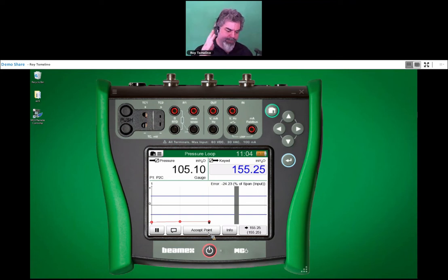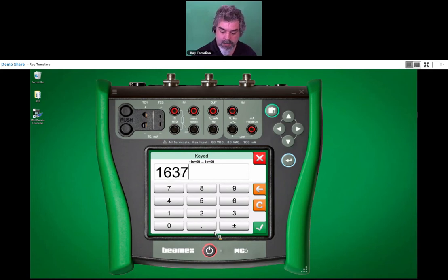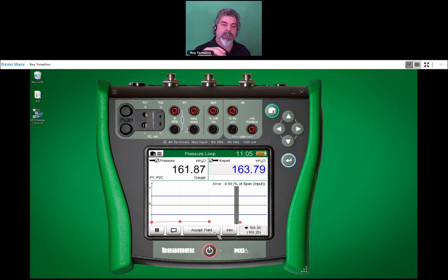So what do? As long as everything is connected correctly, I need to go to 155 now. As long as everything is connected correctly, then I just way overshot it. Then we need to grab the test data as it is. And you know what? 163.79. That's what I'm showing on my DCS, and you can see that it's a similar offset all the way across the bottom. Let me accept this point as well.